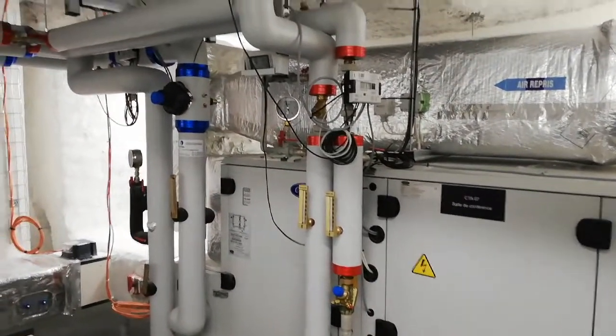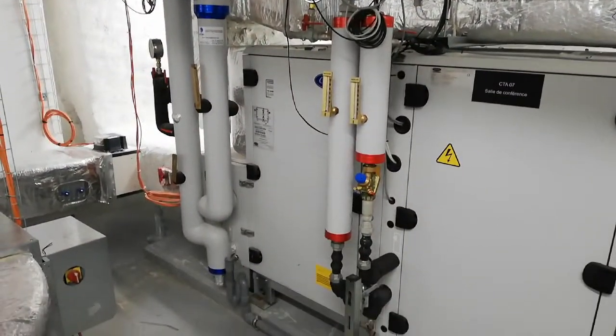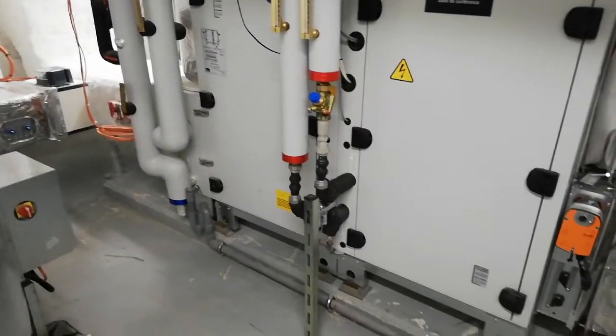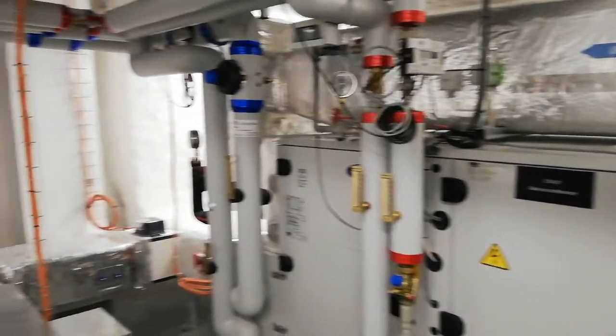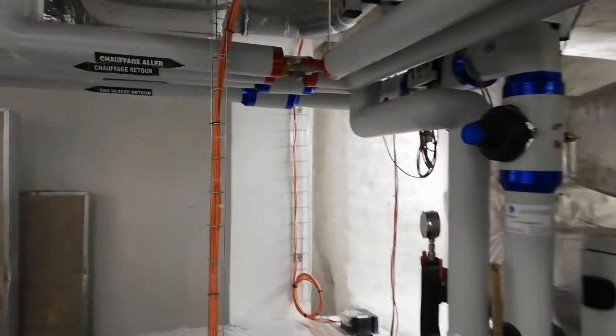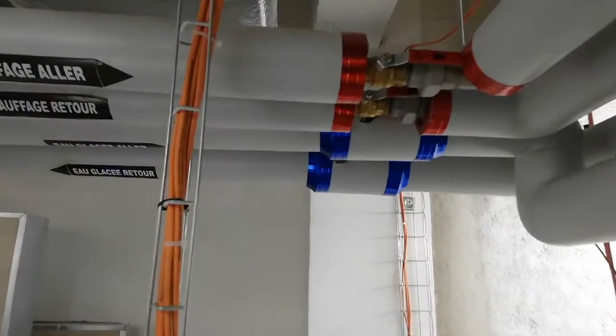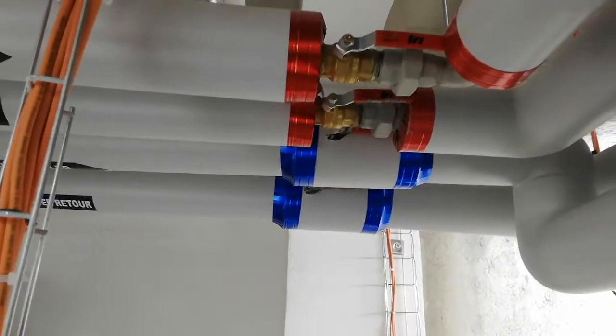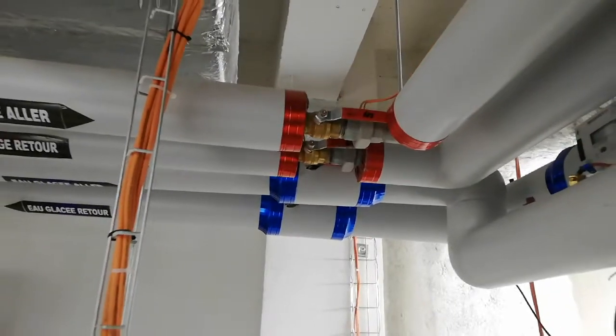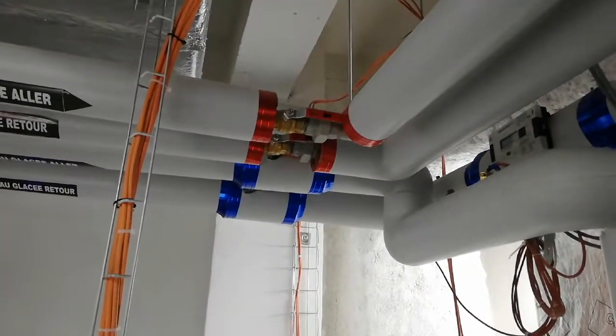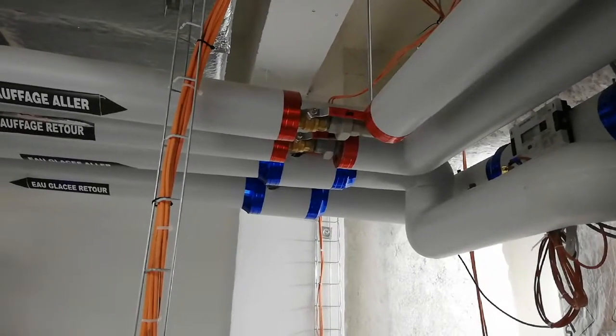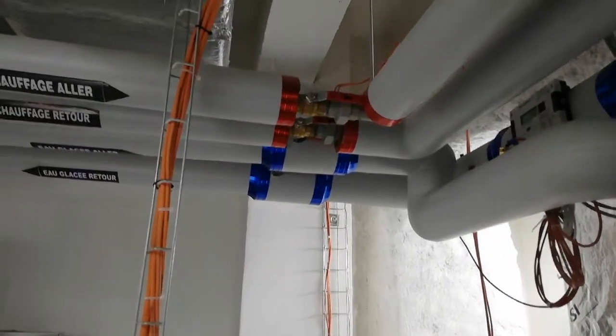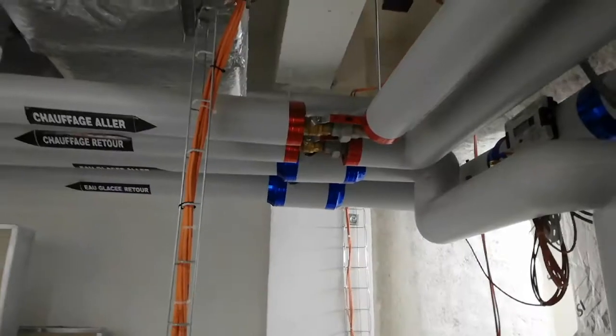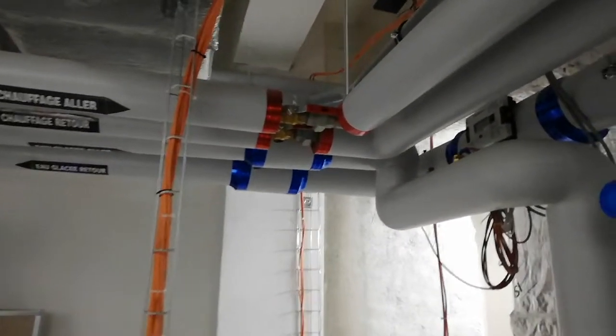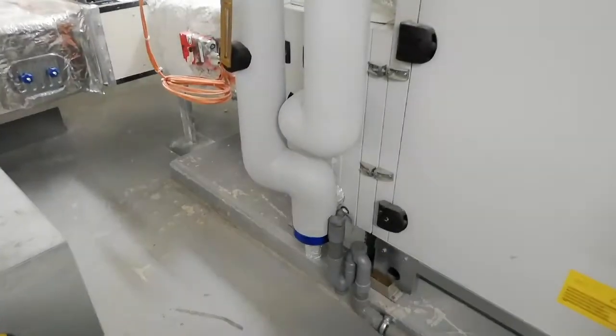This is a dual flow AHU unit with two coils, one hot water coil and one chill water coil. First thing, let's speak about the shut-off valve. Here you have the shut-off valve. It's very important to always put a shut-off valve before any other hydraulic components such as the strainers or the control valve. If you need to do anything like cleaning the strainer, you won't have to drain the whole water system. You would just have to shut off this valve and then drain only these coils using the drain right here.